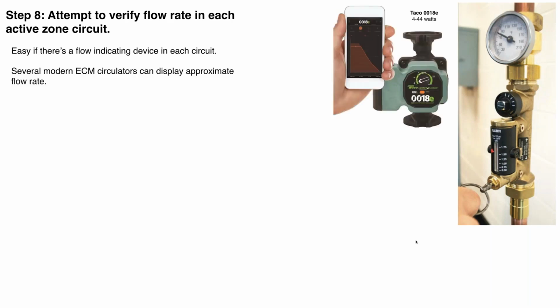Attempt to verify the flow rate in each active zone circuit. Now, if you've got a flow indicating device like a quick setter valve here, that's really easy. Just pull the ring and you're going to get a readout on the flow. It gets a little more challenging if you don't have any flow indicating device, although here's one of the things that has come along that is a help. There's several companies now, Taco, Grundfos, and Xylem, all have small circulators with ECM motors that have Bluetooth capability and can communicate with a smartphone, and they can actually show you the flow rate. It's not lab grade flow indication, but it's enough to at least get you in the ballpark.